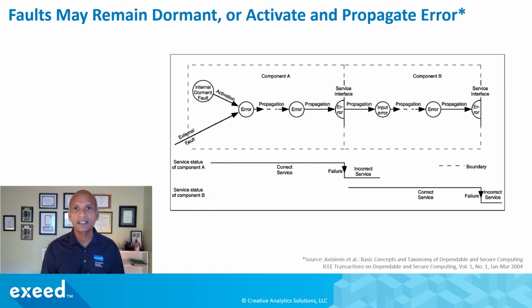Okay, so here is a schematic from the IEEE paper, and I found this pretty illuminating, that there may be a fault in your system, its underlying components, by design or by some other operation, but it may be in what they call a dormant state. So going back to the ankle replacement, maybe the surgeon did not align the implant correctly at implantation. That is a dormant fault. And over time, it'll deteriorate into something more. So it'll progress and maybe subject the mobile bearing component to more stresses than it was designed for. Or maybe something happened in the design that perhaps induced more oxidation or more degradation of the part before it was implanted. So those situations can lead to this scenario, what we call a dormant or a latent fault.